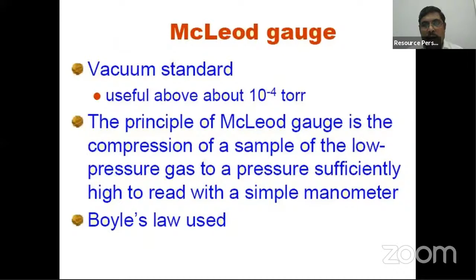The McLeod gauge works based on the principle of Boyle's law. In this gauge, there is a calibrated volume, a bulb whose volume is precisely calibrated. On top of this calibrated volume there is a capillary, and in the capillary there is a calibrated scale attached. The principle is that the unknown low pressure is compressed to a level which can be measured by a simple manometer. So we need to compress the unknown gas pressure to a value at which a simple manometer can measure it.